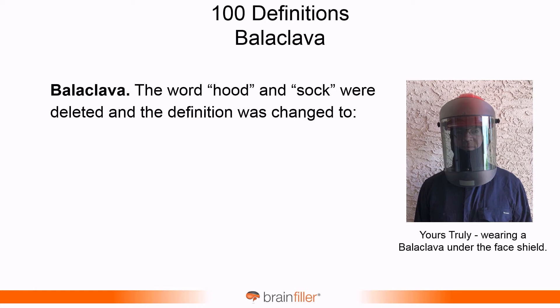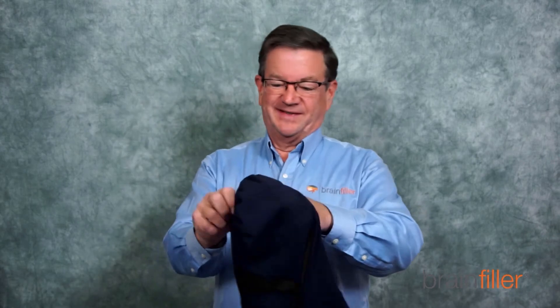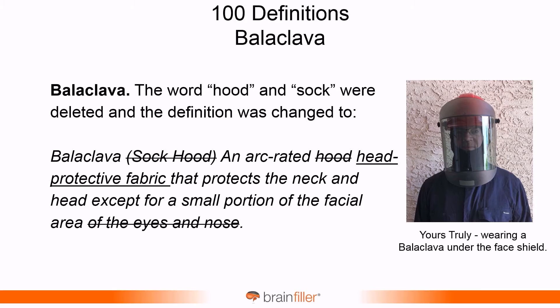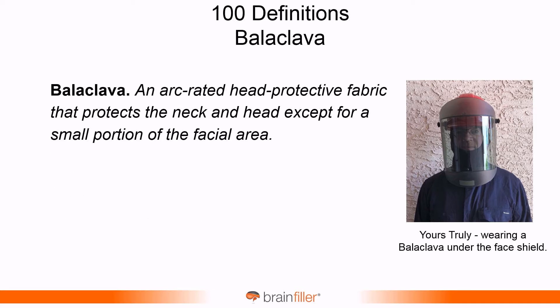The first definition I want to begin with is balaclava. Previously, the definition included the words 'hood' and 'sock.' Looking at a balaclava, it's not really a hood, and you can't really call it a sock. So those two terms were eliminated. It's now defined as an arc-rated head protective fabric that protects the neck and head except for a small portion of the facial area.